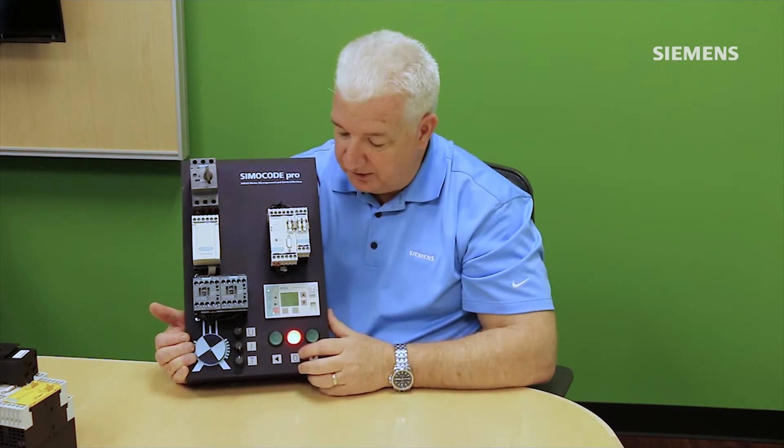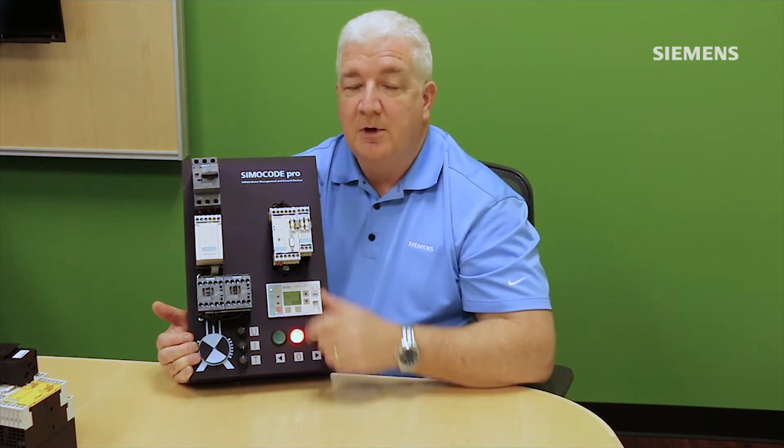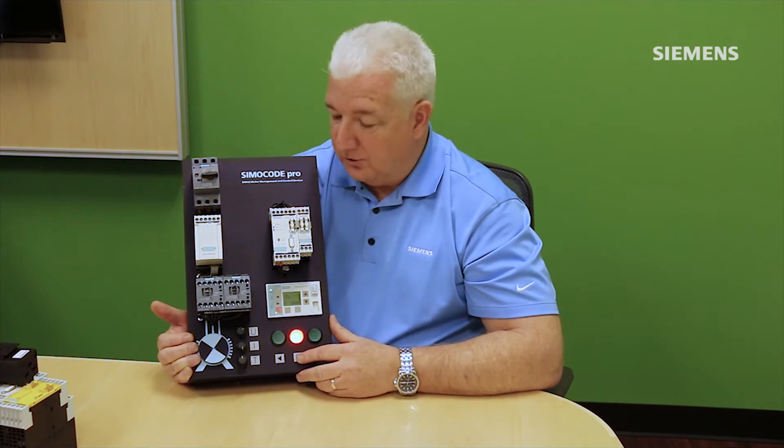Additionally, if the motor is in a run condition and the three-phase supply goes away unexpectedly, the motor had an unexpected stop — SIMOCODE didn't receive a stop command, yet motor current stopped flowing. SIMOCODE flags this as a separate individual fault, aiding in recovery time by giving maintenance personnel better diagnostic information about why the system shut off and how to get it back up faster.